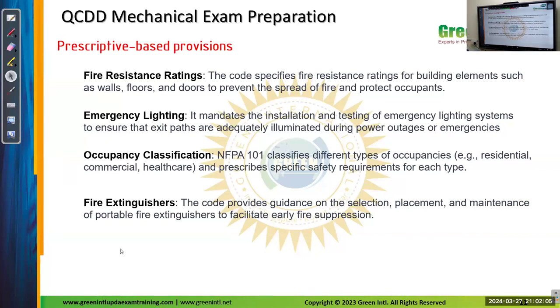Emergency lighting. It mandates the installation and testing of emergency lighting systems to ensure that exit paths are adequately illuminated during power outages or emergencies. So you have to make sure that the standby power systems or battery power system is working or not. Emergency power lighting system is working or not.